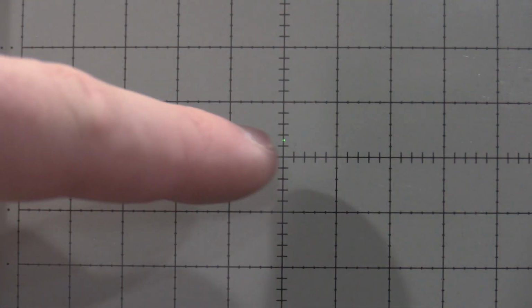So we're checking the horizontal amplifier balance. I have the magnifier out to ×10. What the document wants me to do is rotate the horizontal volts per division control down to 2 volts, and we're looking for minimal shift horizontally from the spot. There's one, that's 10, 5, 20, 1.5, that's 0.2, so it's actually real good. So that doesn't need adjustment at all.